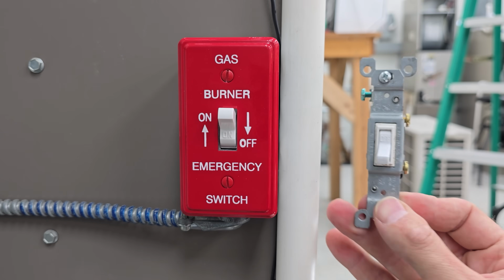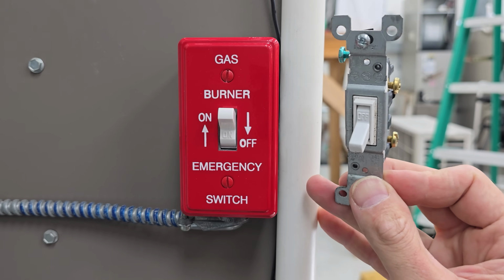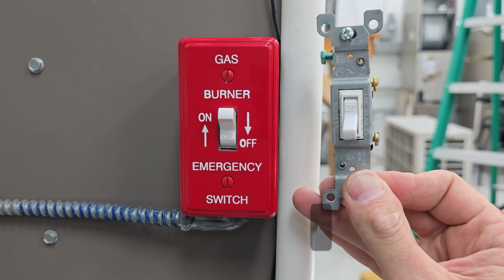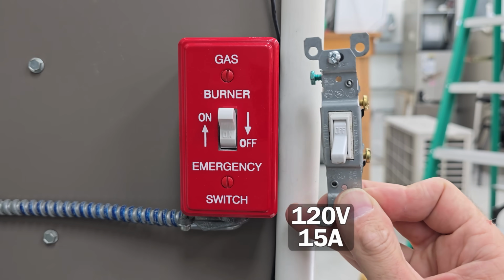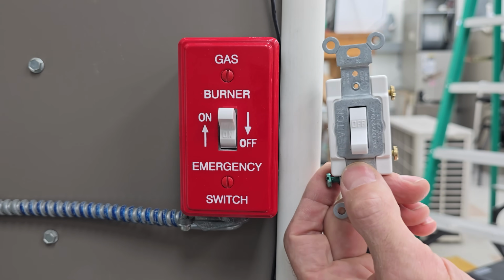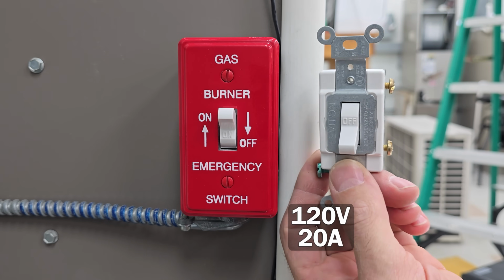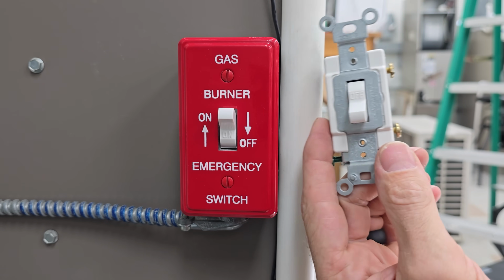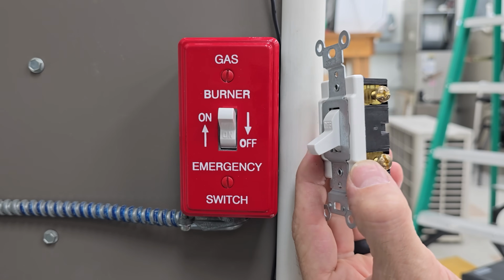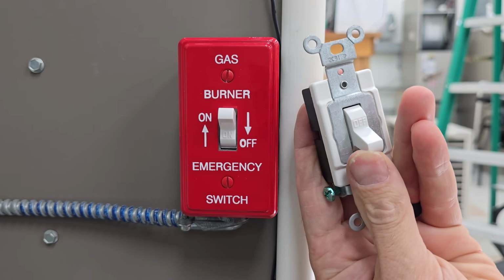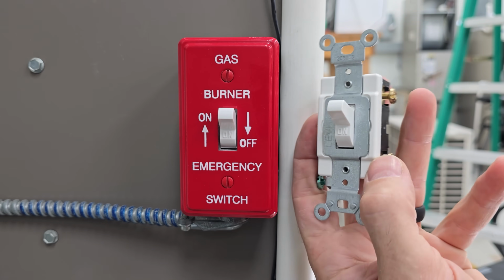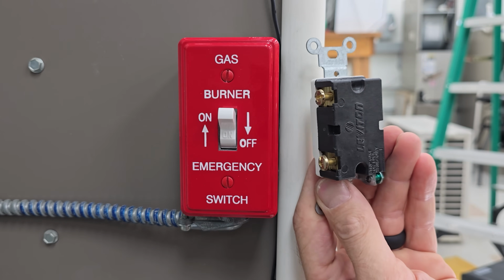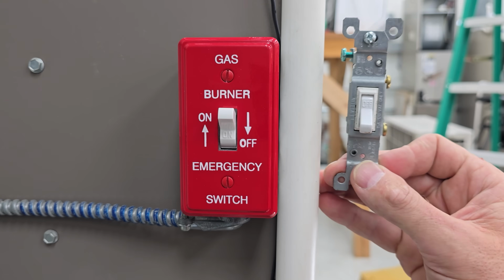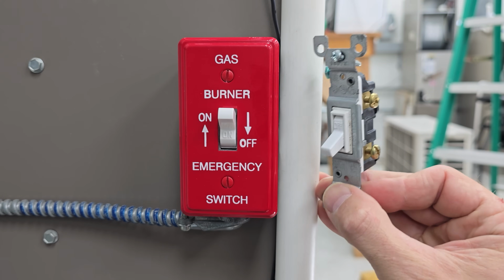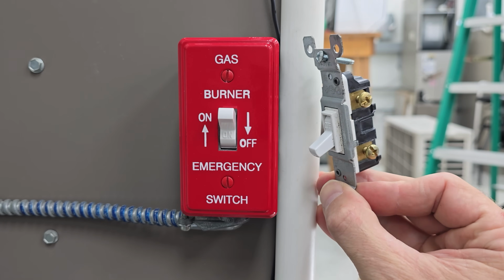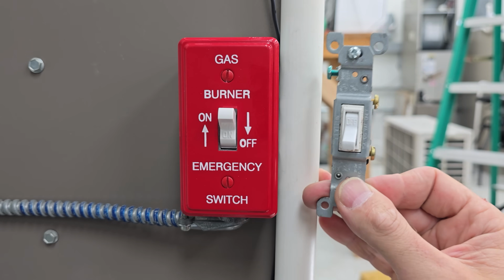I notice a lot of people end up using these little light switches for the gas furnace. Now these are 120 volt 15 amp rated, which is the same ratings of the furnace, but I highly recommend that you use these 120 volt 20 amp rated switches. They're going to last longer. They're going to have a tighter spring mechanism for when you are closing the switch, so when you are turning it on. And the thing with it is the contacts inside end up getting burnt on these little 15 amp light switches. And that's due to the high electrical current from the blower motor of the furnace. And so I find these failing a lot out in the field.